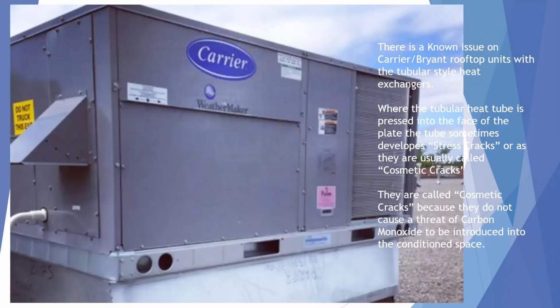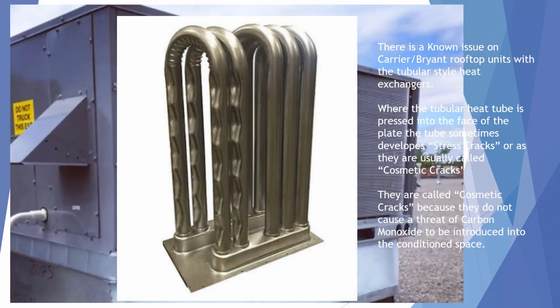Here's the known issue on Carrier Bryant rooftop units with the tubular style heat exchangers. Where the tubular heat tube is pressed into the face of the plate, the tube sometimes develops stress cracks, or as they are usually called, cosmetic cracks. They are called cosmetic cracks because they do not cause a threat of carbon monoxide to be introduced into the conditioned space.